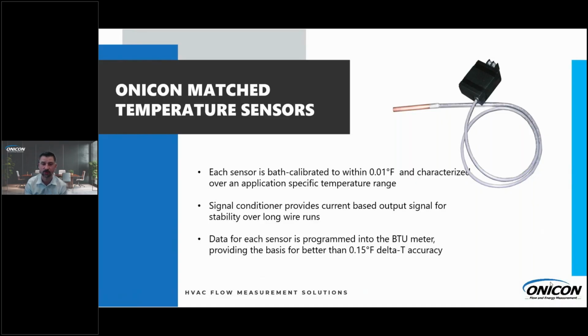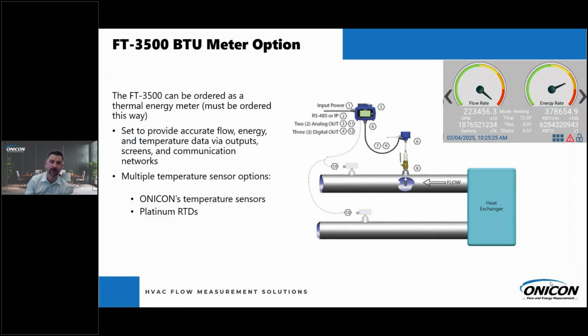So what ONICON does is we're not just providing a calibrated flow meter, but we're providing calibrated and matched temperature sensors. So even if it's a little bit off on the supply, it's going to be a little bit off on the return in the same exact direction, which is providing a very accurate delta T measurement, which is where that BTU measurement is coming from. So now you have the calibrated flow meter, calibrated and matched temperature sensors going back to the transmitter, and our transmitter is doing that BTU calculation so many times a second.